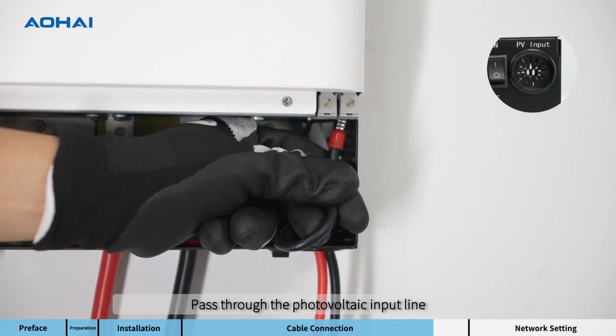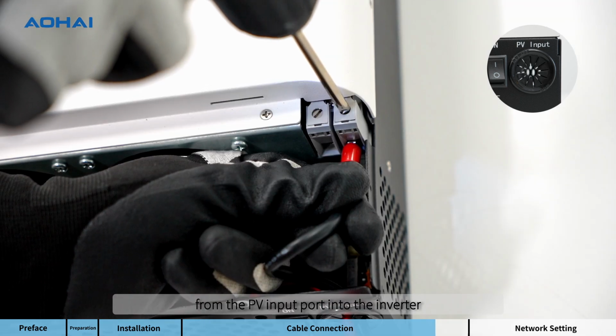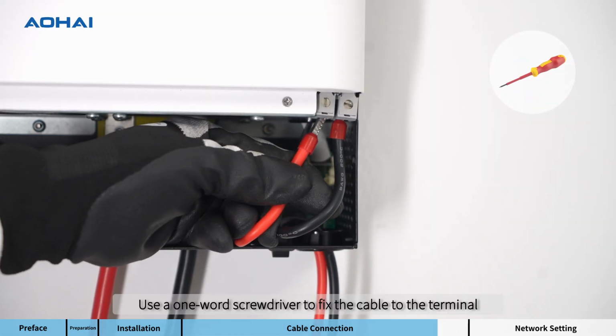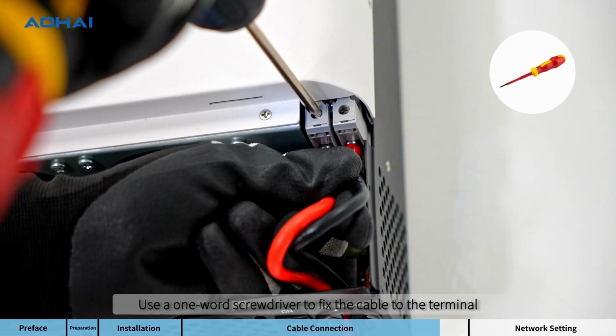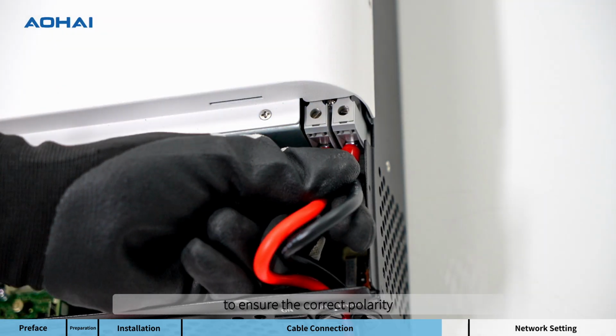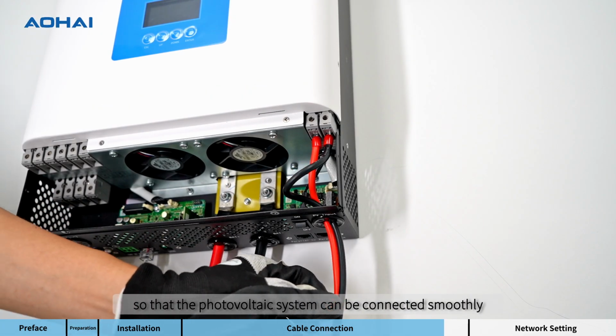Pass through the photovoltaic input line from the PV input port into the inverter. Use a single-slot screwdriver to fix the cable to the terminal, ensuring the correct polarity so that the photovoltaic system can be connected smoothly.